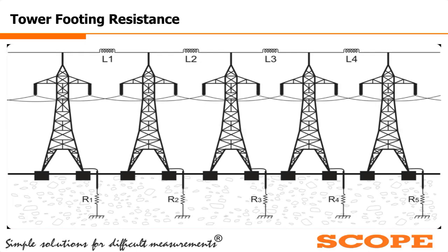So that's why we will require a high frequency earth resistance measurement technique. The model which we are offering, TM25r, operates on 25 kilohertz frequency. Now I will explain why this high frequency is required in tower footing resistance measurement. Let us consider a signal generator which is injecting a current of 25 kilohertz frequency. Now what we will do is inject this current between the terminal E and the far end terminal H, and we will measure the voltage difference with the help of the voltage electrode. In this way we will measure the tower footing resistance.